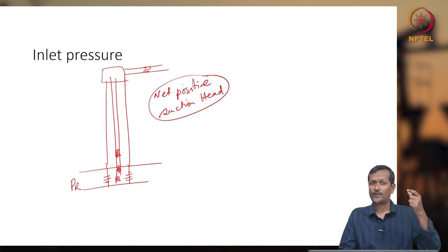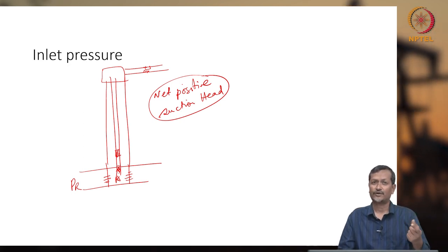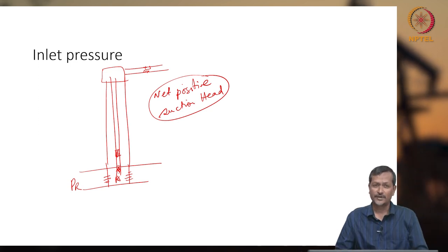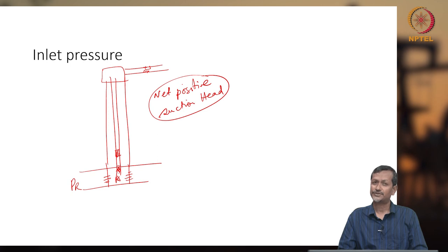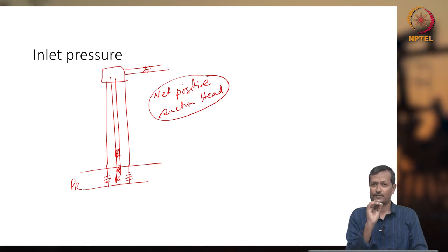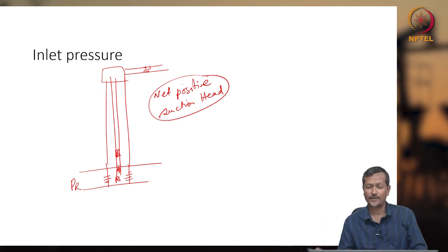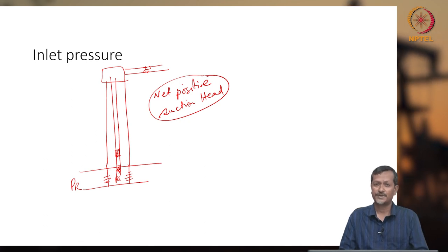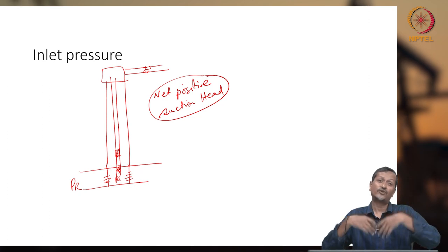But when you are using it in an oil and gas wellbore, again when pressure goes down because you are not maintaining a certain amount of pressure, the gas will come out from your liquid. The gas will interfere with the pumping operation, resulting in vibration, noise, cavitation, erosion and maybe some other issues also. So you have to maintain a certain amount of pressure, especially since a centrifugal pump needs a higher inlet pressure because it is sucking a high amount of fluid.